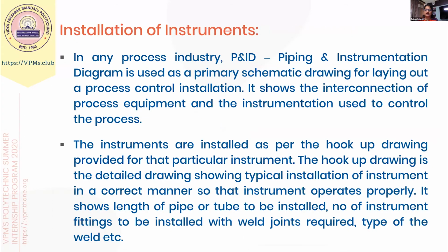Then, like in any process industry, the P&ID, that is the piping and instrumentation diagram, is used as a primary schematic drawing for laying out a process control installation. It shows the interconnection of different process equipment and the instrumentation used to control the process. So this is a P&ID. And the instruments which we were discussing are installed as per the hookup drawing. There are different tags for each instrument, and for each tag there is a standard drawing known as a hookup drawing, showing how that instrument is to be installed at the site in the correct manner so that it will operate properly.